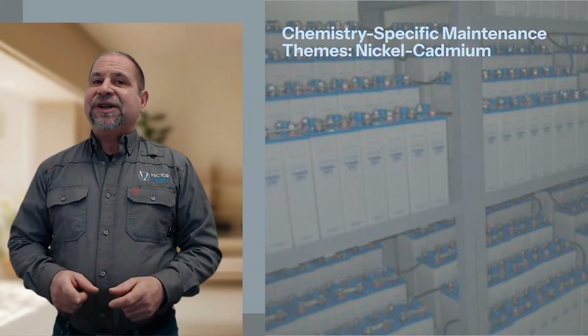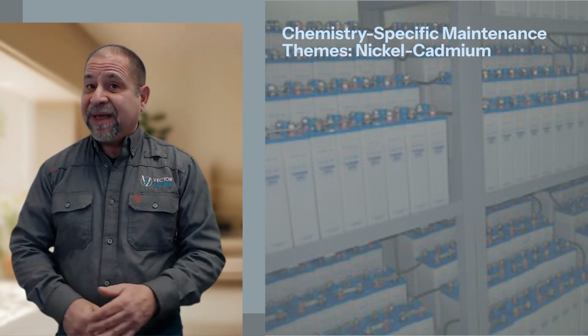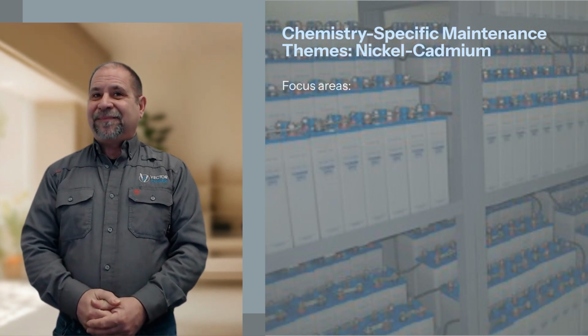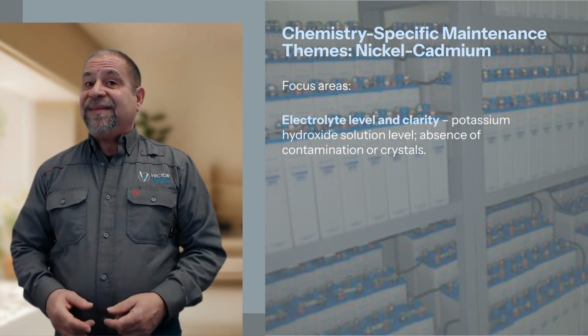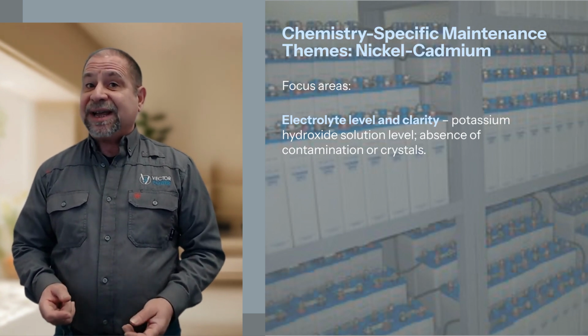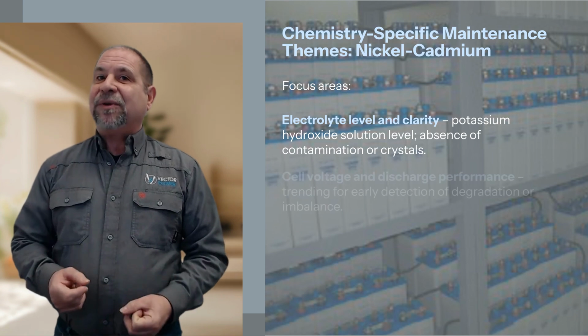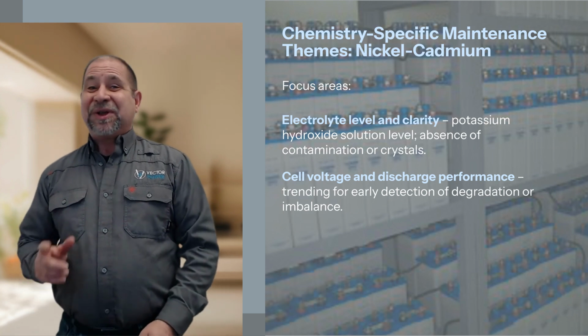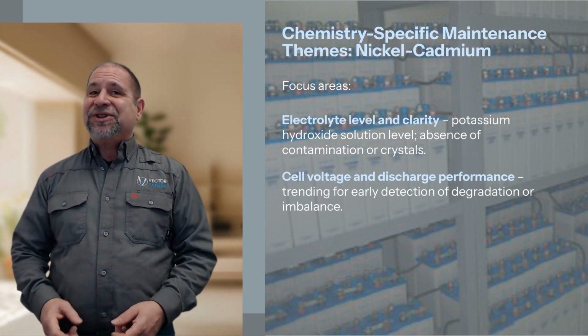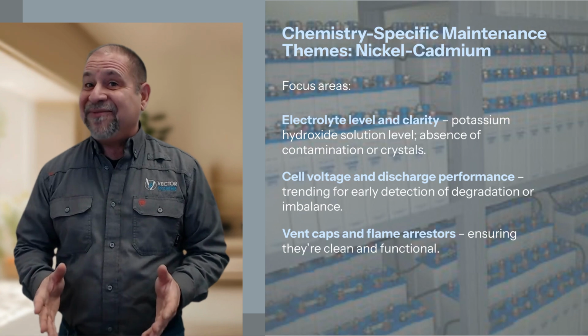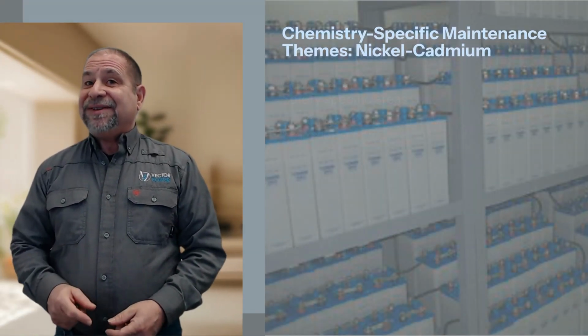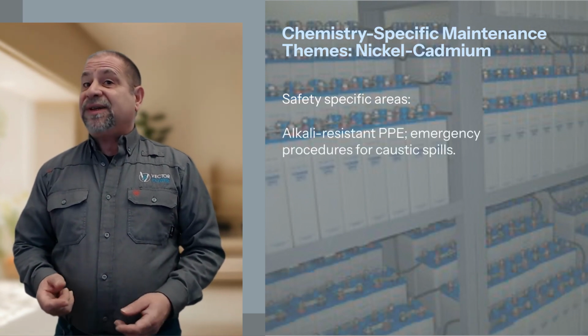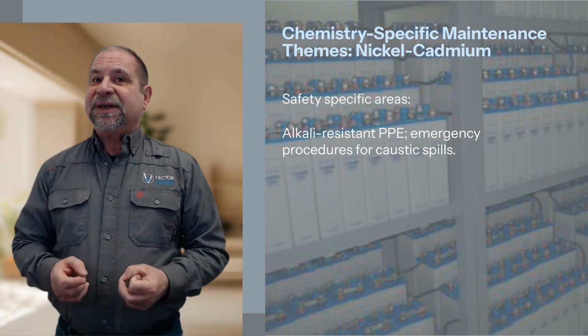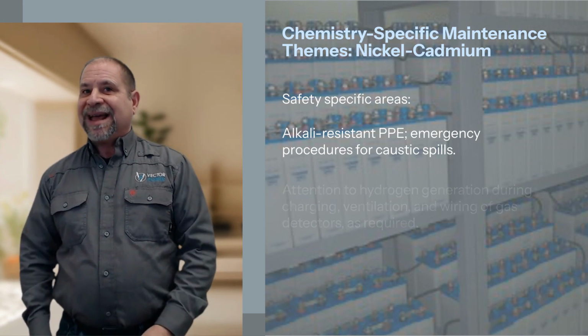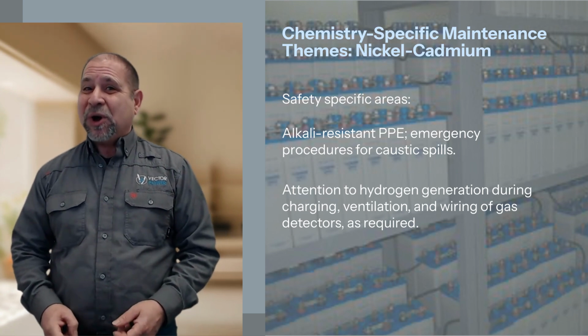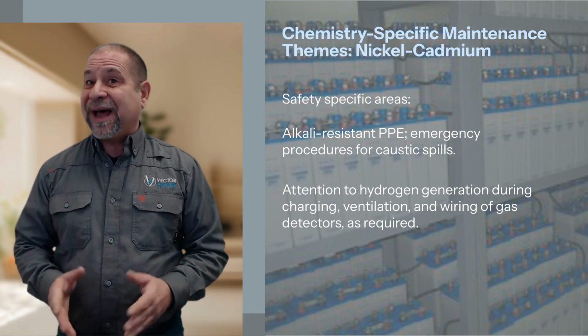Next, let's look at chemistry-specific maintenance themes for nickel-cadmium batteries. Focus areas will include electrolyte level and clarity. Check potassium hydroxide solution level, check for the absence of contamination or crystals. Cell voltage and discharge performance, trending for early detection of degradation or imbalance. Check vent caps and flame arresters, ensuring they're clean and functional. Safety specifics. Use alkali-resistant PPE and develop emergency procedures for caustic spills. Maintain attention to hydrogen generation during charging, ventilation, and wiring of gas detectors as required.